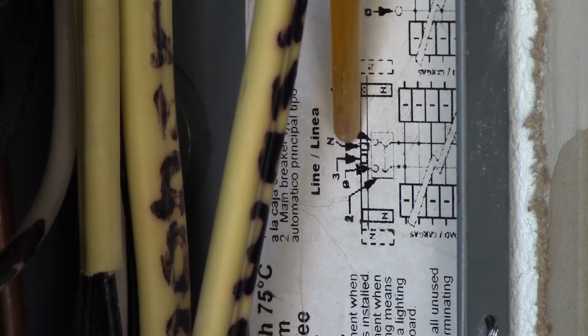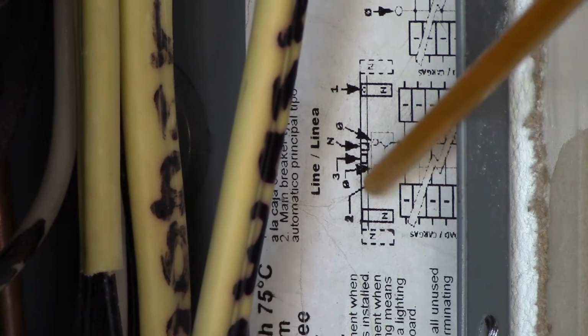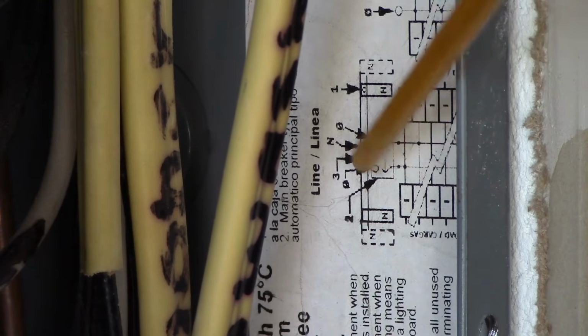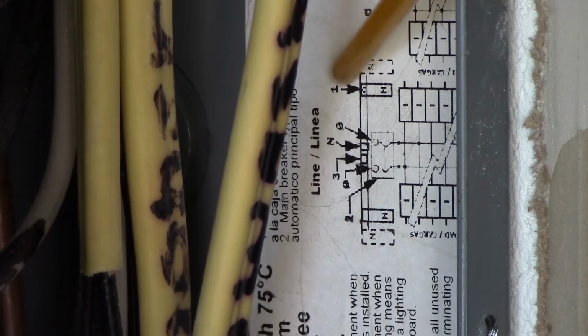Okay, now anywhere in here, some of the older ones you might have a main bonding jumper that can be anywhere on this side or anywhere, but in this panel it tells you exactly where it needs to be installed. So just be careful. And again, the screw in this case was green. But if it was prior to 1990, it might not be green. It might be of a silver finish. You just got to search for it on the panel. Take your time and look and see if you can find it to make sure.